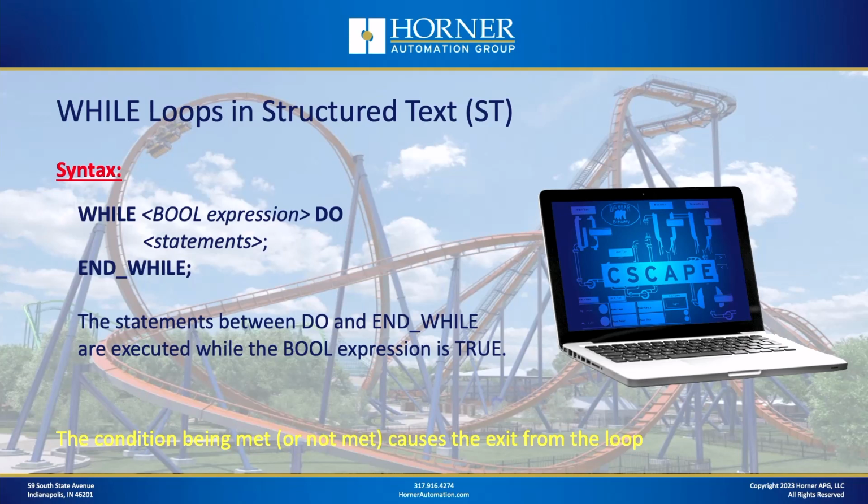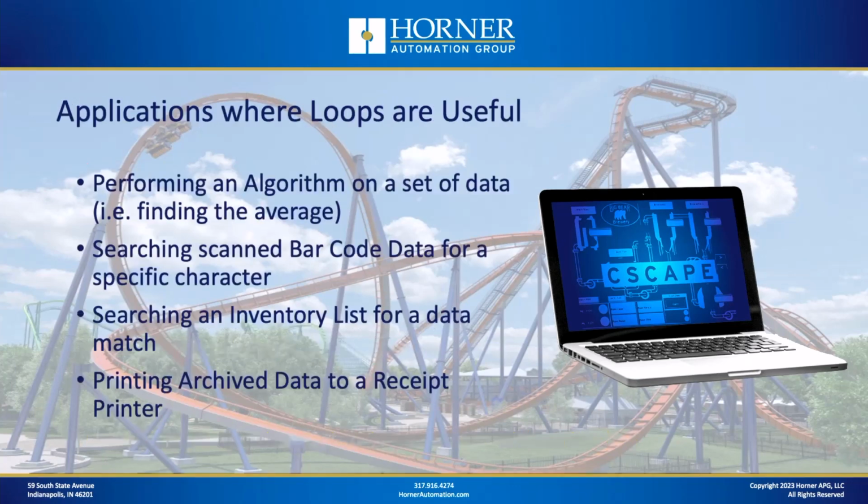And therefore, if that condition is never false effectively, then you're never going to exit from that loop. So that scan, that particular scan that the while loop is executing on will never end. And therefore, you're going to have an infinite loop and your controller is going to reset. So we have to be much more careful anytime we are executing a loop a variable number of times to make sure that that variable number of times isn't infinity.